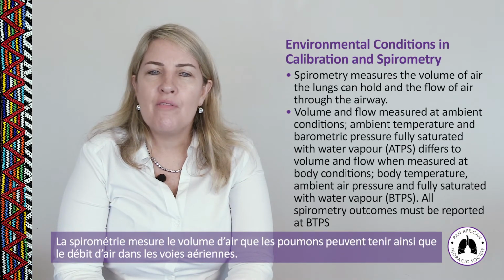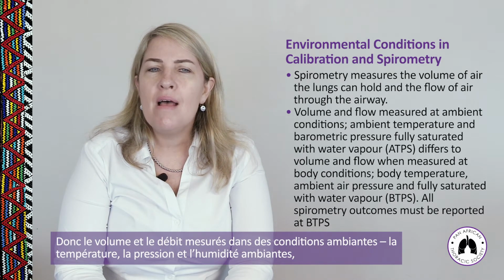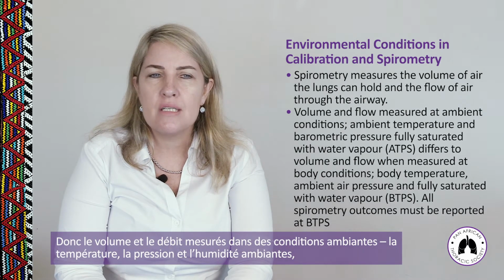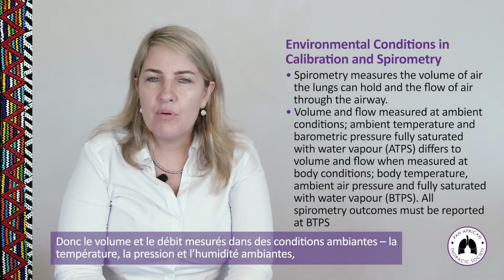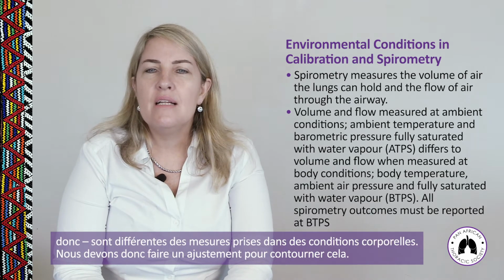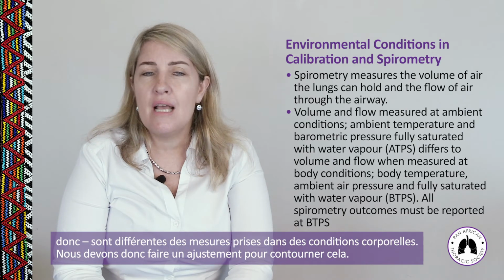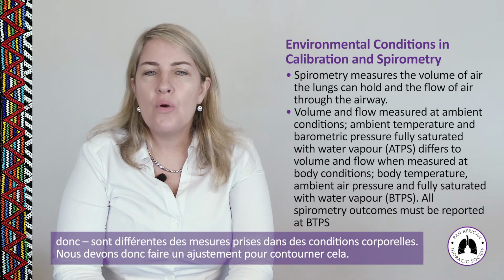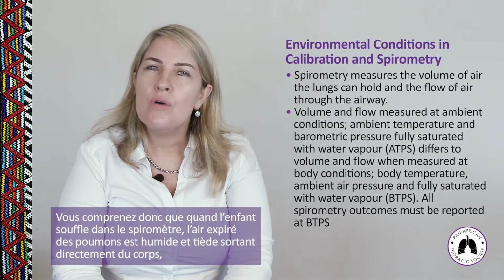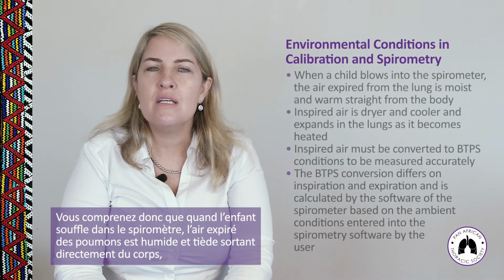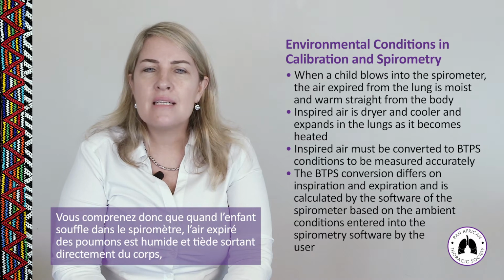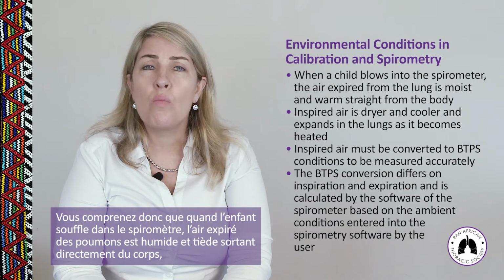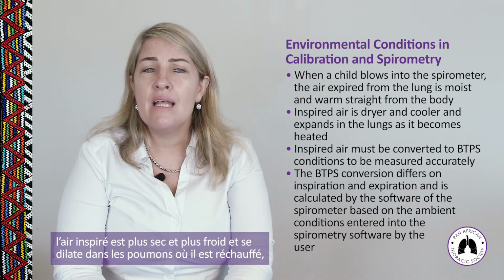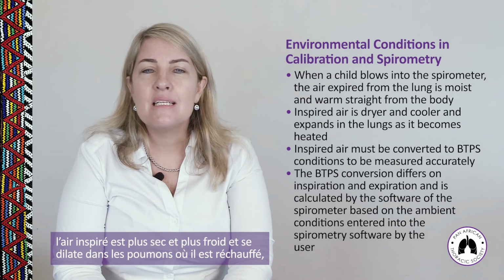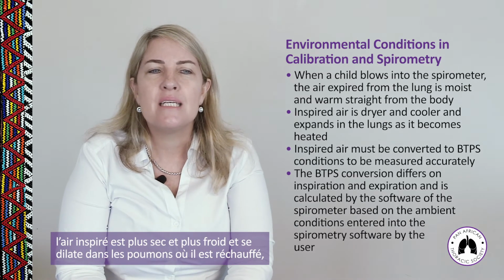Spirometry measures the volume of air the lungs can hold and the flow of air through the airway. So volume and flow measured at ambient conditions, that's ambient temperature, pressure, and humidity, differs to the volume and flow measured at body conditions. So we need to make an adjustment for that. You do understand then that when a child blows into the spirometer, the air expired from the lungs is moist and warm straight from the body. Inspired air is drier and cooler and expands in the lungs as it becomes heated.